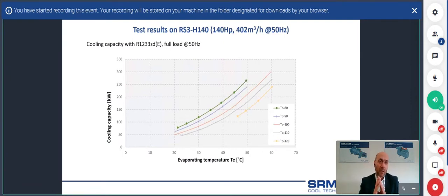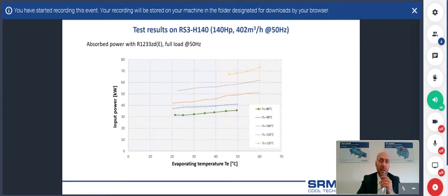This additional graph is showing the cooling capacity of the system, where on the x-axis we have the evaporating temperature expressed in Celsius degrees, and on the y-axis we have the cooling capacity expressed in kilowatts. These different curves express the cooling capacity at different condensing temperatures, between 80 and 120 degrees. Of course, the cooling capacity at 120 is lower than at 80 because we have major losses or lower efficiency in the compressors. In this graph, it is shown from the other side the input power, which indicates on the reverse that the input power increases with the increasing of the condensing temperature. This is because the condensing pressure is much higher at 120 degrees than at 80 degrees C.